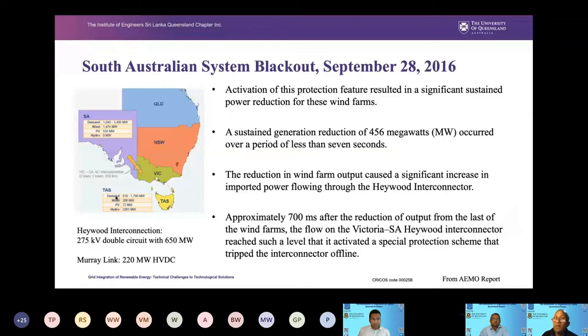So the activation of the fault features in this one, even though there was what we call a fault ride-through capability put in place in the wind farm, the power had to be reduced in those wind farms to protect those turbines. So as a result of the sustained fault in the system, a generation reduction of about 450 megawatts resulted from these wind farms. As a result of the fault, the wind farm reacted and then reduced the supply.